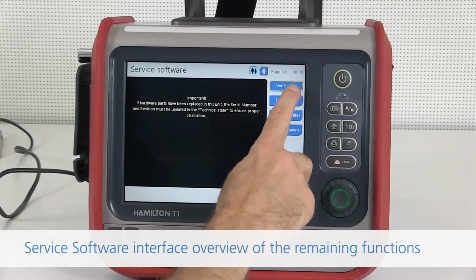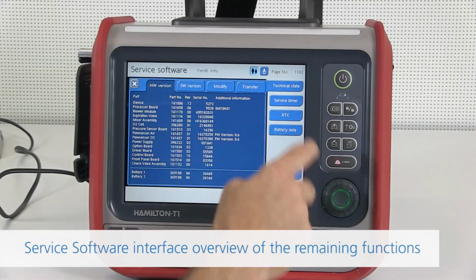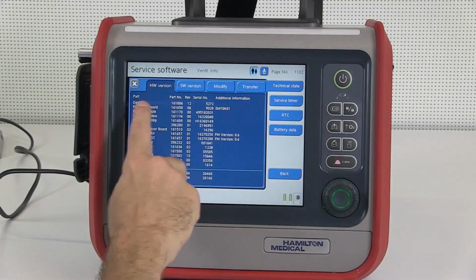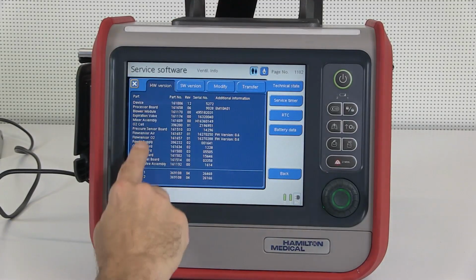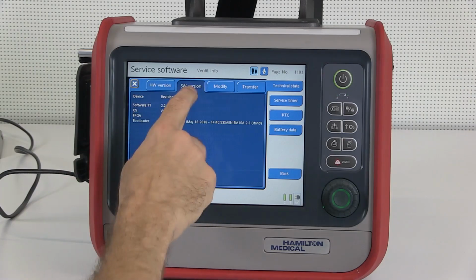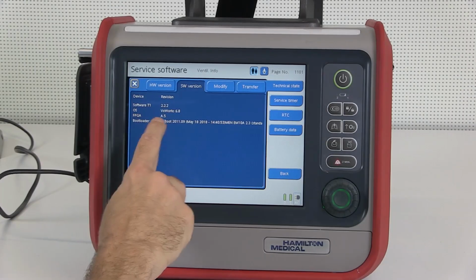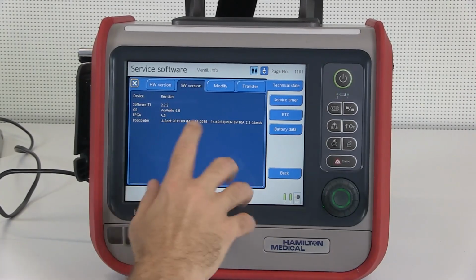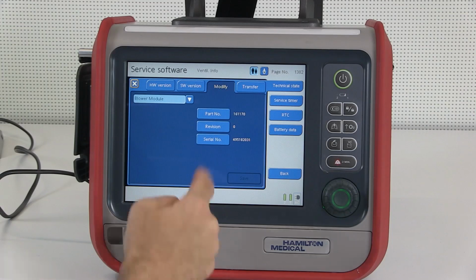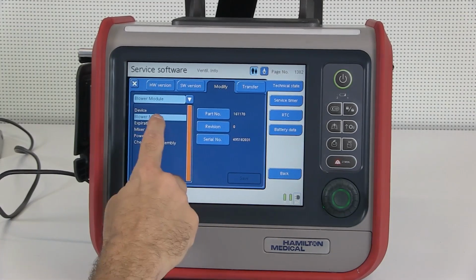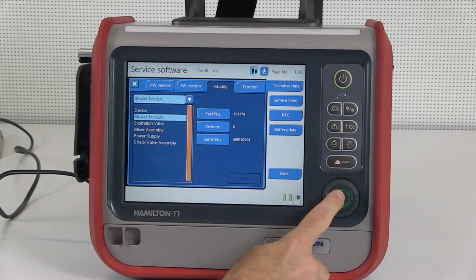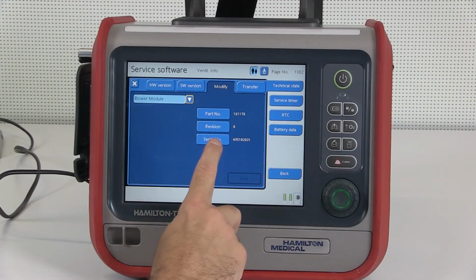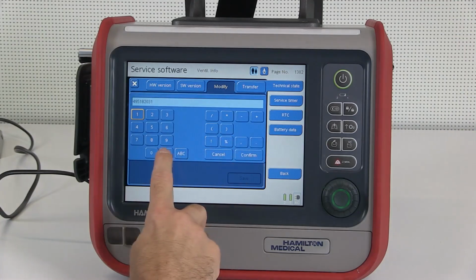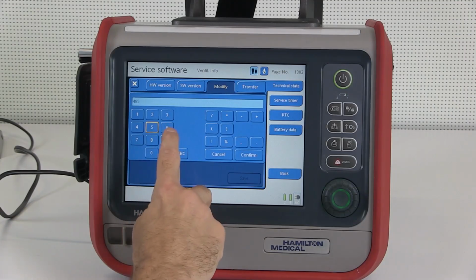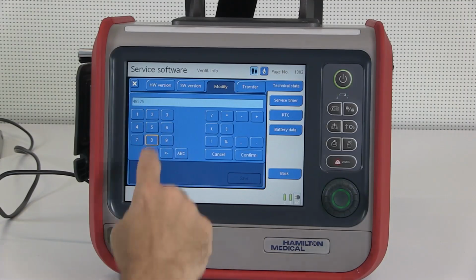Touch Ventilation Info, then Technical State. Here we can see the device part, revision and serial numbers, as well as each part. SW version shows the specific details of the installed software version. If you replace one of the following parts, go to the Modify tab to manually update the part, revision and serial numbers. This applies to the device if you replace the control board, the blower module, expiratory valve, mixer assembly, power supply, and the check valve assembly. For other parts, the part, revision and serial numbers are updated automatically.